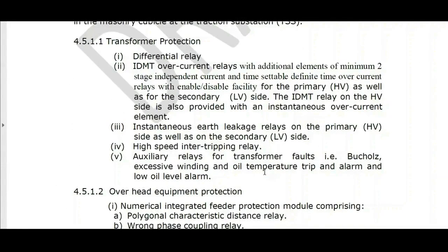Buchholz relay, winding temperature, oil temperature. So these are the things that you might have seen. Buchholz is a gas actuated relay. We normally keep this relay on top of the transformer itself. Whenever a fault occurs inside the transformer, there will be some kind of heat or fault current generated. Due to that, bubbles will be formed inside the oil. When bubbles form, by nature they move towards the top, because oil is heavy and the bubble is light. So the bubble will move from the bottom to the top.